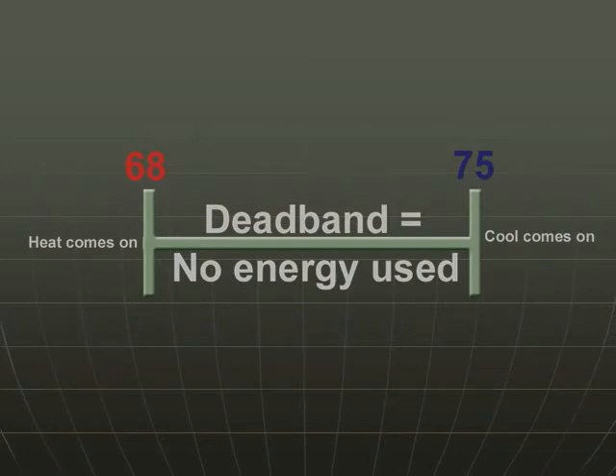The deadband also turns off the air going to a zone if it's within the range between the heating and cooling set points. So if the cooling set point is configured at 75 degrees and the heating at 68 degrees, then there is no air going to the space if the zone temperature is between 75 and 68 degrees.